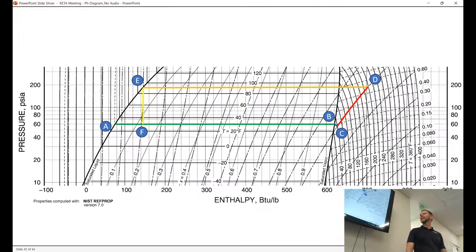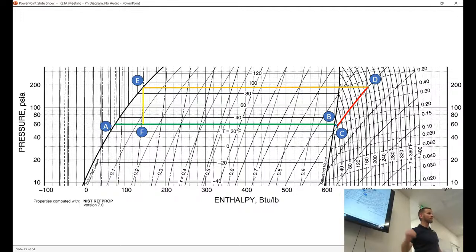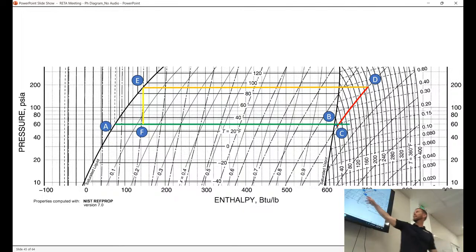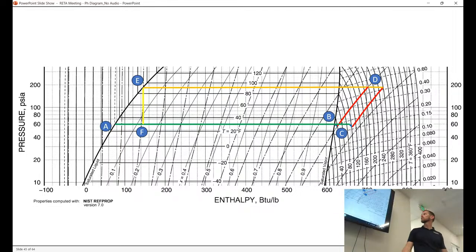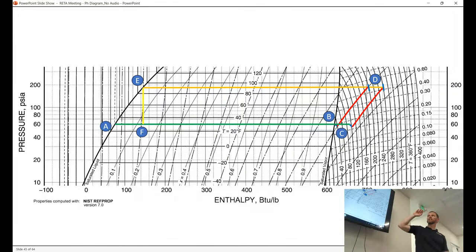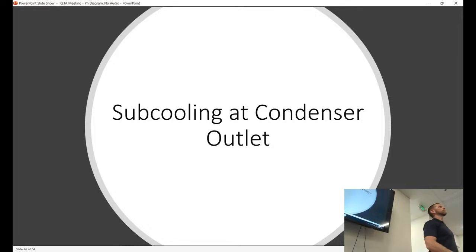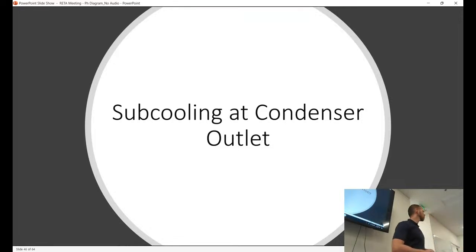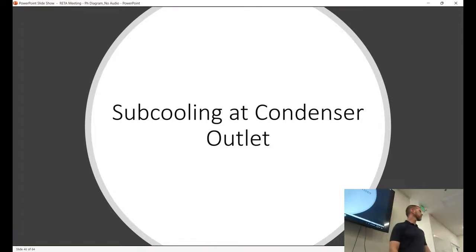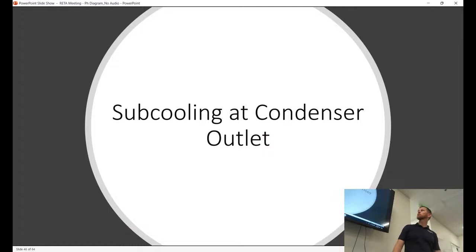Now what happens with superheat at the compressor inlet? Let's say your evaporator load increases in a DX system, so it's not big enough — you're evaporating all the liquid and now you're just adding heat to the vapor. You're increasing the temperature of the ammonia at the outlet of the evaporator, going out further here, and our compressor discharge will be way up. It's increased our temperature quite substantially — that's extra heat that needs to be rejected by the condenser, and we've increased our discharge temperature. Okay, these are all negative effects so far. So let's look at some good things — the benefit of subcooling.